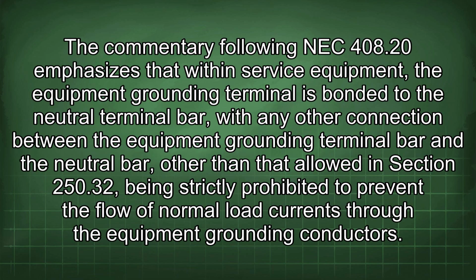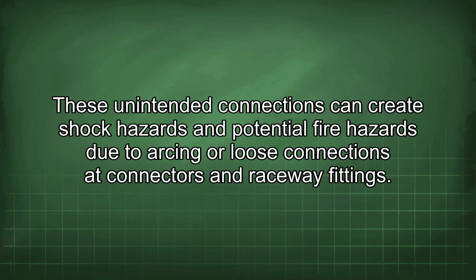The commentary following NEC 408.20 emphasizes that within service equipment, the equipment grounding terminal is bonded to the neutral terminal bar, with any other connection between the equipment grounding terminal bar and the neutral bar, other than that allowed in section 250.32, being strictly prohibited to prevent the flow of normal load currents through the equipment grounding conductors. These unintended connections can create shock hazards and potential fire hazards due to arcing or loose connections at connectors and raceway fittings.